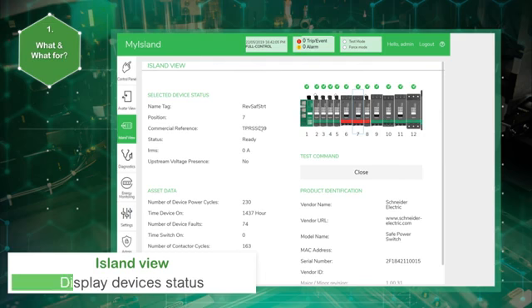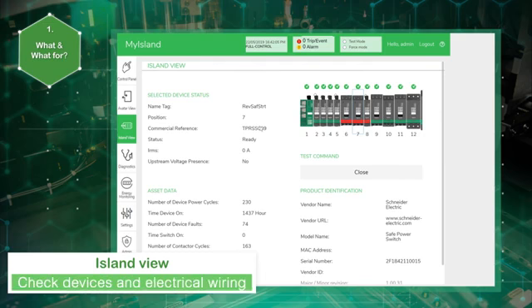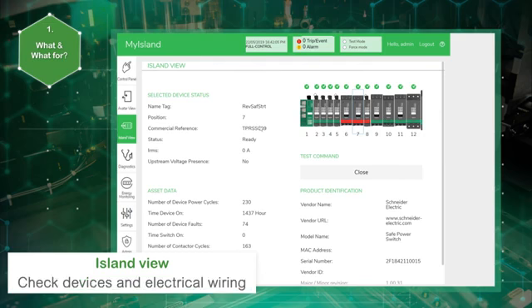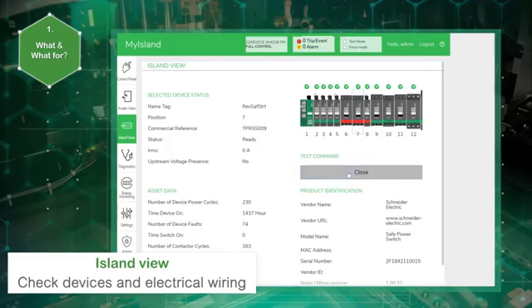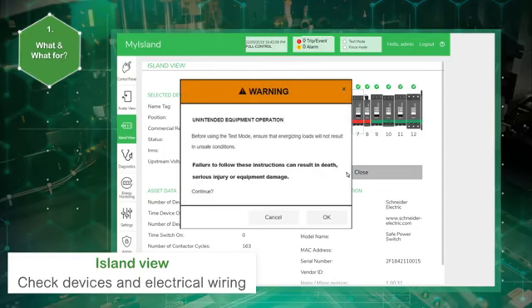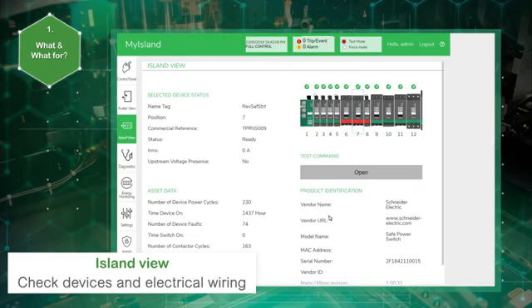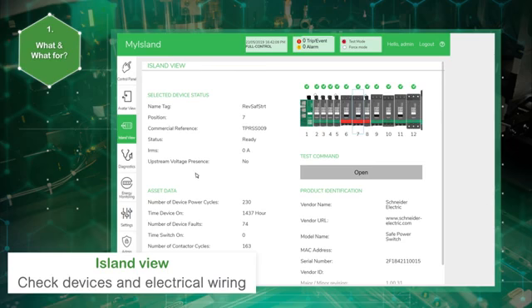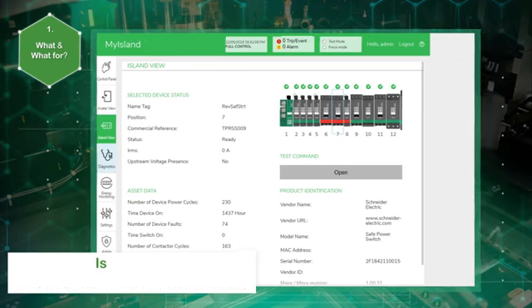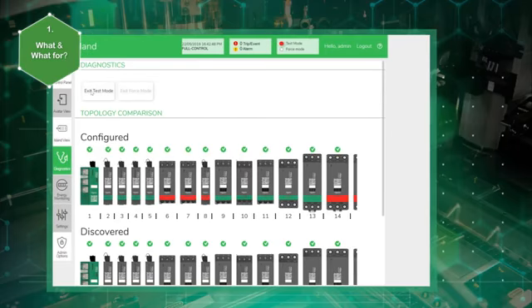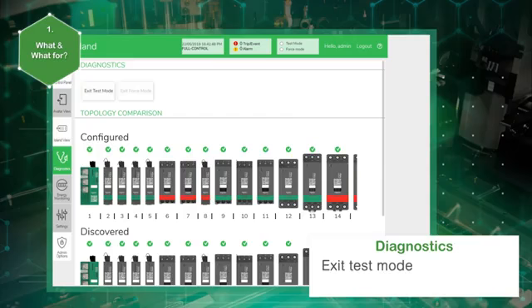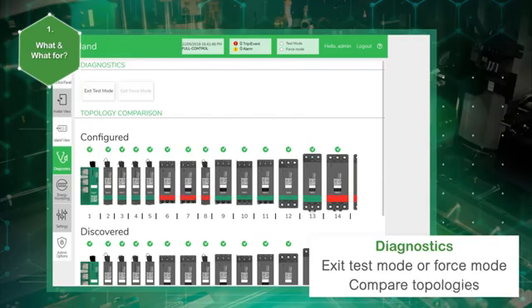To perform diagnostics, it is possible to test each device of the island under test command, click to close or open command. The test mode indicator flashes red and the load status LED of the tested starter is flashing green-red. Once you complete force or test mode, please make sure to exit force and test mode.